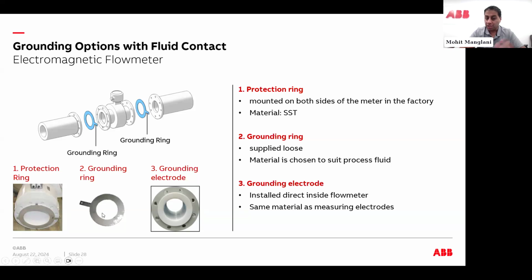Number 2, for liners like hard rubber, we'll give you a wafer ring. You can sandwich it between your mag meter flange and your mating flange. This is exactly where they go. So imagine your mating flange. You'll have a gasket, ring, gasket, mag meter, gasket, ring, gasket, and then the mating flange. So the consideration of a grounding ring, the inconvenience of it is it does add to the overall length of the meter flow tube. And so you have to accommodate that in your calculations. But the nice thing is it'll give you that nice stable output.